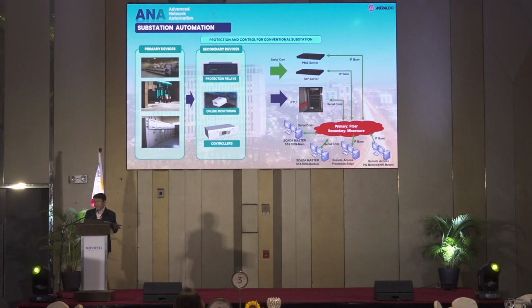Shown in the slide is a typical old substation automation solution, comprising several analog interfaces, though some secondary devices are microprocessor-based. All components of the substation, from the high voltage switchgears, power transformers, and medium voltage switchgears, are copper wired to various secondary devices like relays, controllers, meters, and condition monitors.